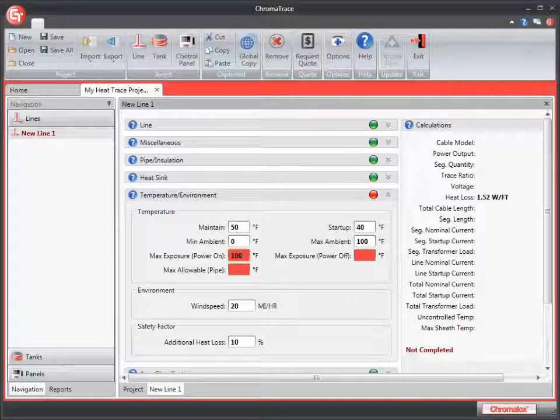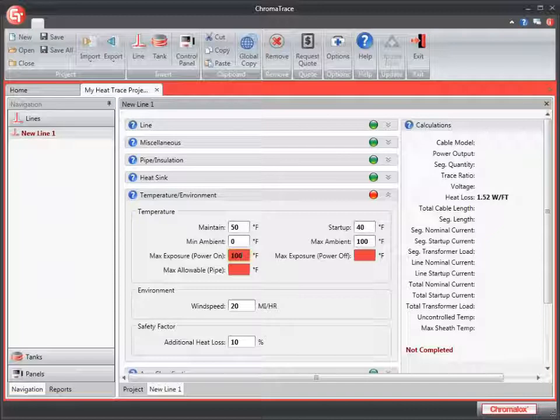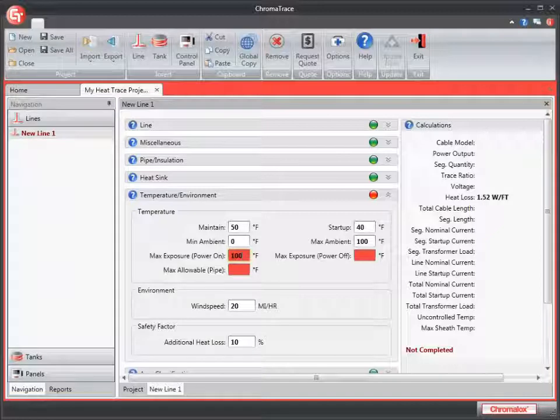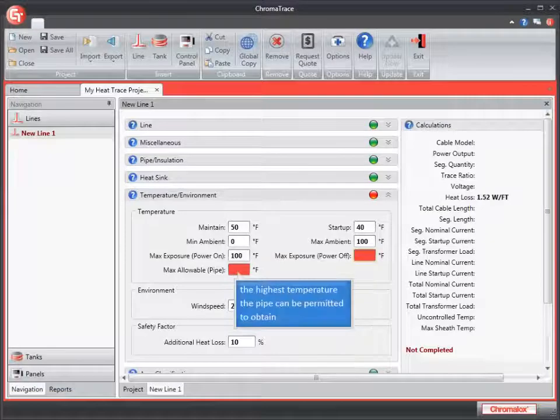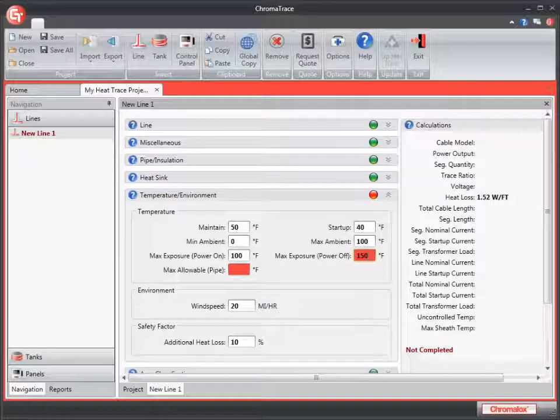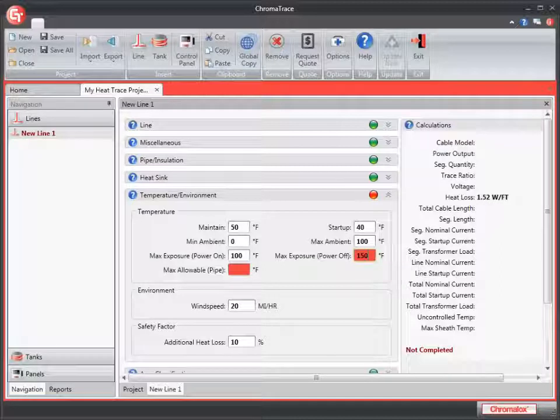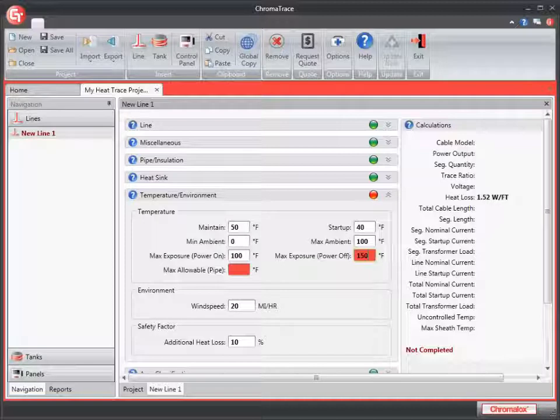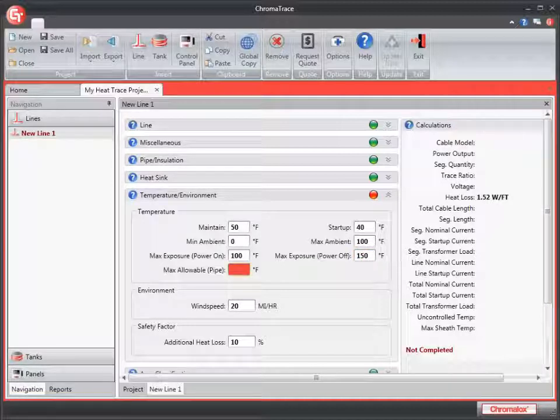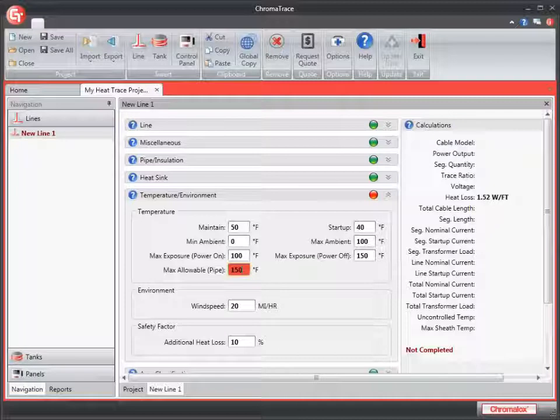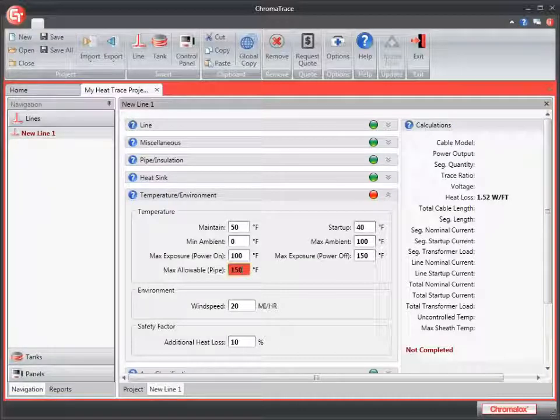Maximum exposure for power on is the highest anticipated ambient pipe or fluid temperature to which the heating cable will be exposed continuously with the power on. I'm going to enter 100 for this value. Maximum exposure power off is the highest anticipated pipe or fluid temperature to which the heating cable will be exposed continuously with the power off. I'm going to enter 150 for this one. Maximum allowable for the pipe is the highest temperature that the pipe contents can be permitted to attain. We'll put 150 in here.